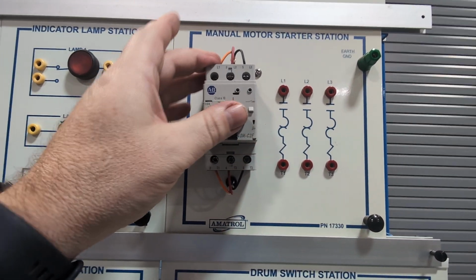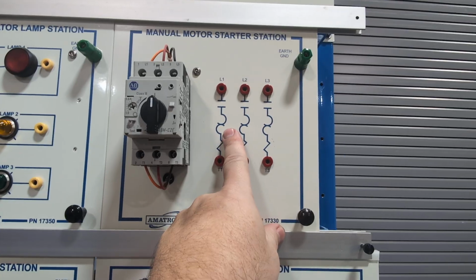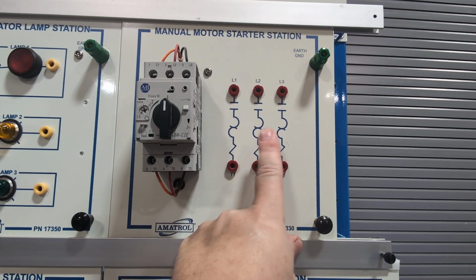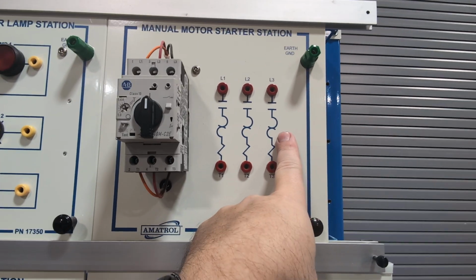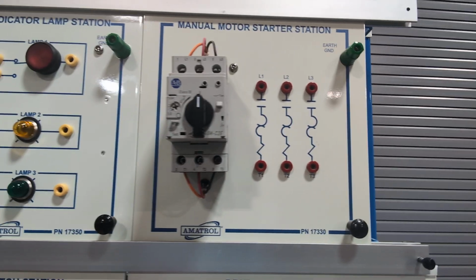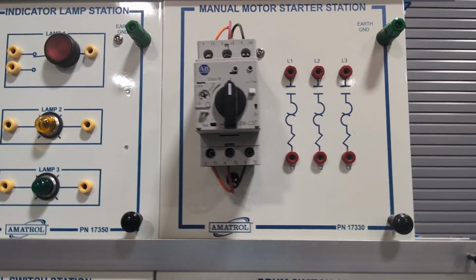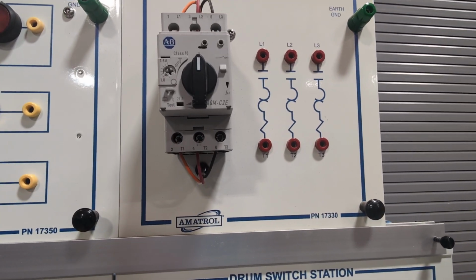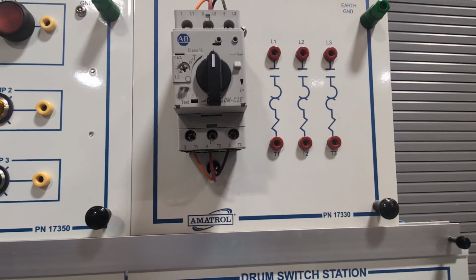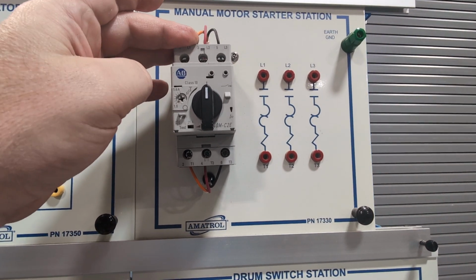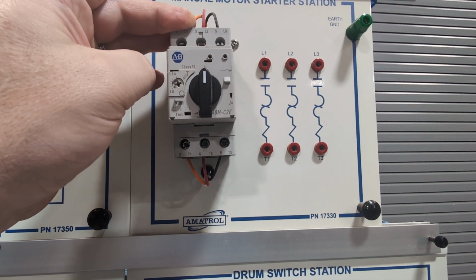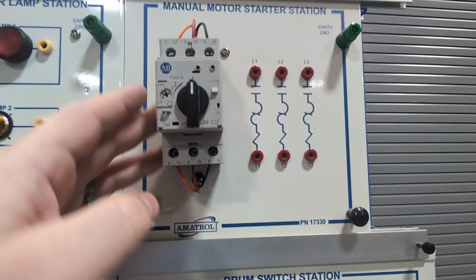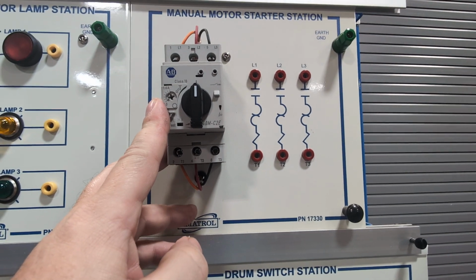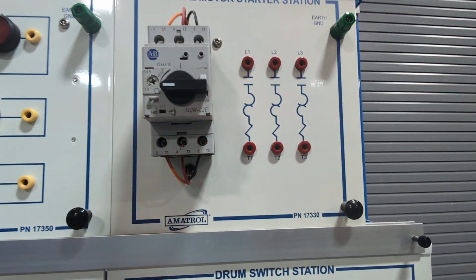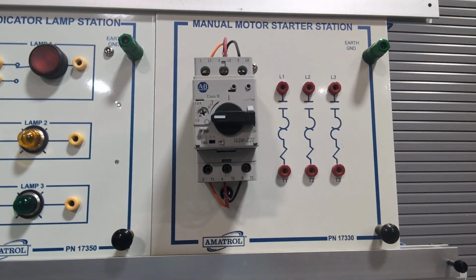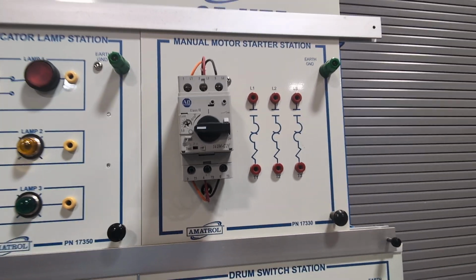Okay. This is a motor starter, but it also has this symbol that means overload. Overload indicates when a motor, which is specifically supposed to run at so many amps, gets past so many amps, or when it's hot. I've had it where it's been hot outside and still tripped from that. The overload uses temperature to indicate and trip, keeping the motor from burning up. This is a manual motor starter.